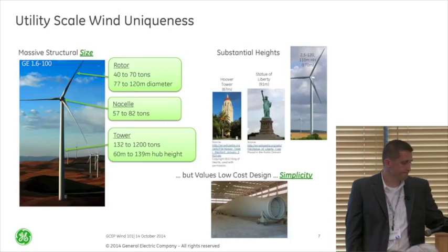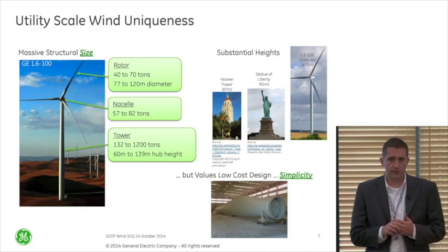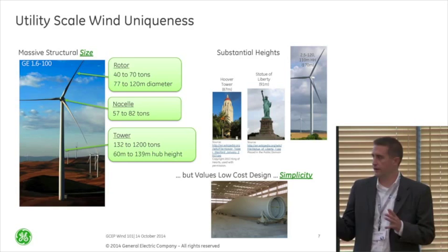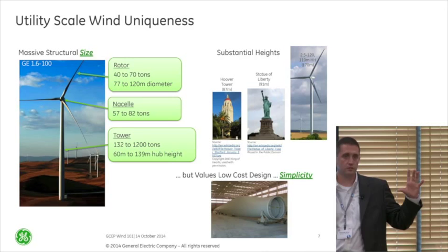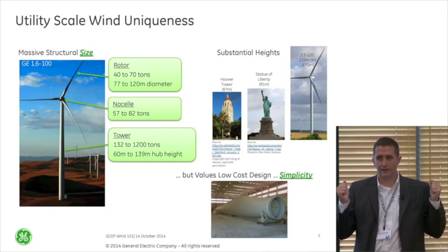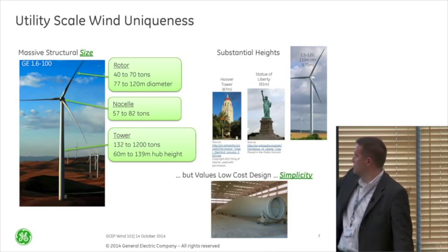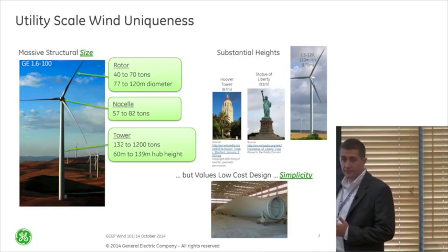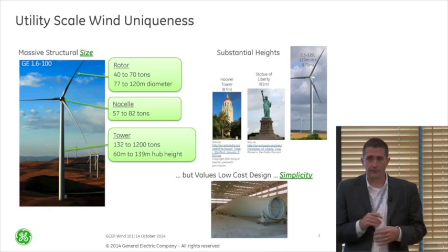There are really two major points that make this technology different from anything else we've done in energy generation. The first is the size — this thing is absolutely huge. I'm trying to extract energy from a fluid — air — with a density of about 1.2 kilograms per cubic meter, very low density, so I need to make these things massively big. Our 1.6-100 has a 100-meter rotor diameter on top of an 80-meter tower hub height. The weights are substantial: the rotor is about 50 tons, the nacelle another 60 or 70 tons, and the tower is huge.